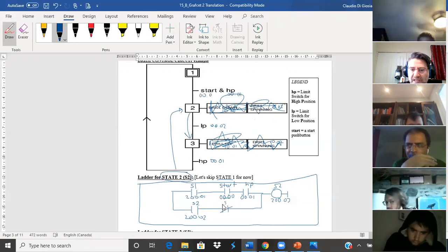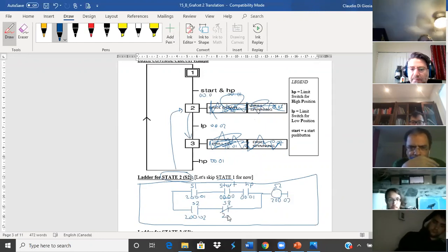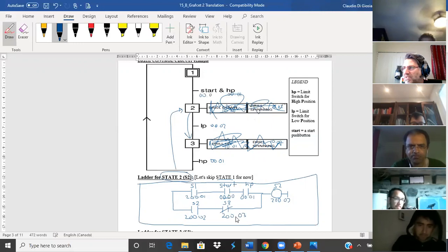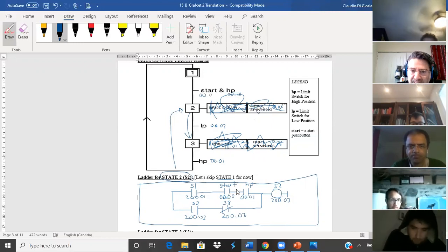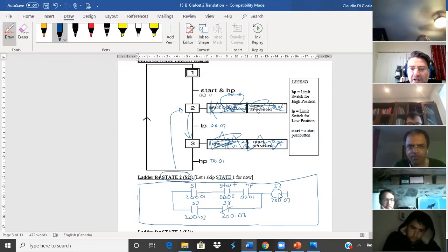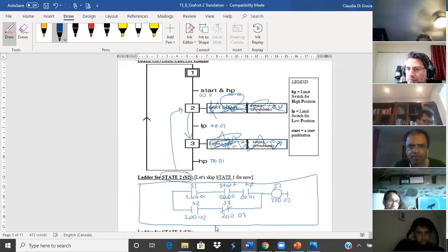When I get to state three, state three will deactivate the maintain here — so this is 200.03. You have to repeat this over and over again. How do I activate a state? Previous state and previous condition. How do I maintain a state? With itself. How do I deactivate a state? With the next state. No thinking involved — just apply those rules.